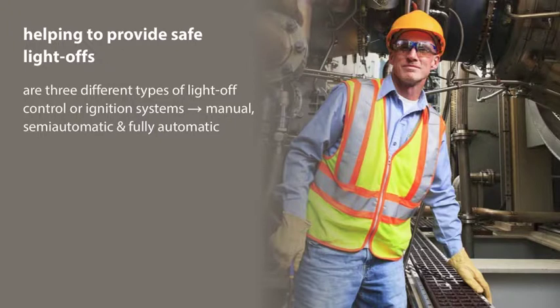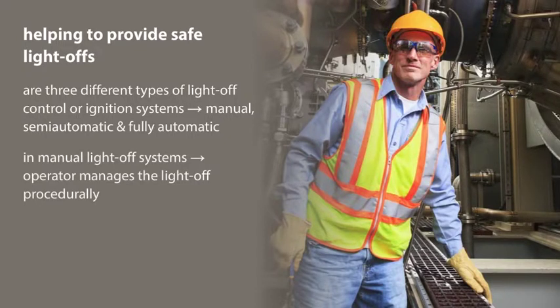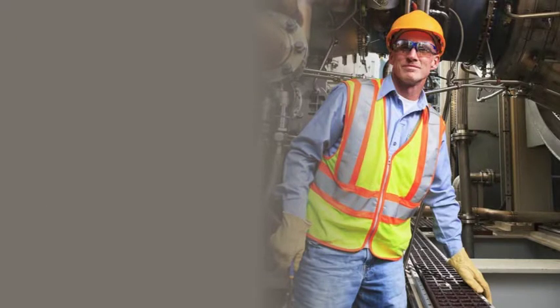Helping to provide safe light-offs. There are three different types of light-off control or ignition systems: manual, semi-automatic, and fully automatic. In manual light-off systems, instead of a BMS system, an operator manages the light-off procedurally. This would still include a purge to make sure that a vessel or combustion chamber is kept safe from fuel-air mixtures. The operator then carefully manages the insertion of some type of torch or electrical spark igniter to the pilot or main flame at low fire for light-off to occur when valves may be manually opened.